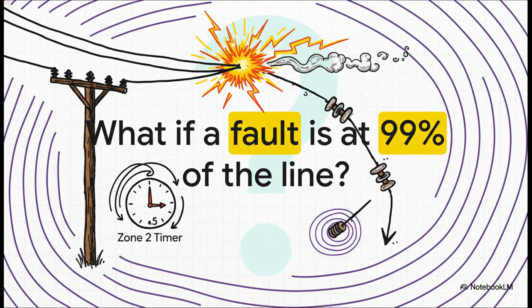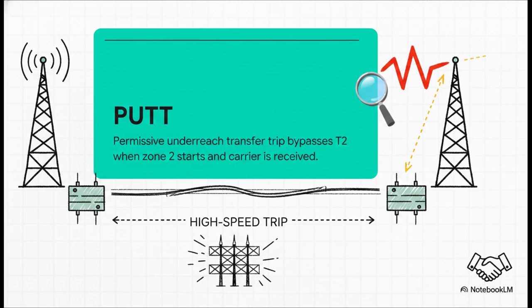We need speed. So the fix here is actually getting these relays to talk to each other. Enter the PUTT system, which stands for Permissive Underreach Transfer Trip. It's essentially a high-speed communication channel, usually over fiber optics or microwave, linking the two ends of the line. If the relay at the far end sees a severe fault in its instant Zone 1, it immediately fires off a carrier signal to our local relay. The second our relay gets that signal, it completely bypasses that half-second delay of Zone 2 and triggers an instant high-speed trip. Teamwork literally saves the grid.